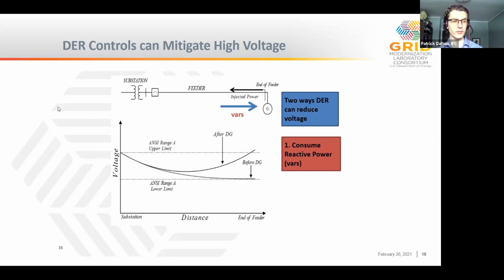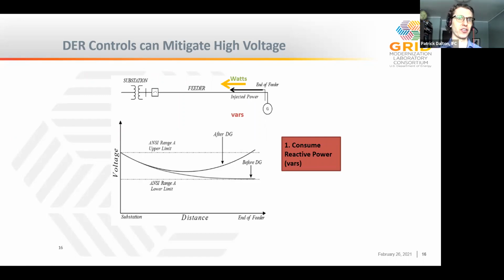The other way, which is a little less desirable, is to reduce the watts — a lower degree of energy production at that time. That's generally reserved as a backup option, because it affects the economics of the DER. And if the system is counting on this energy, it's important to try not to curtail that energy production unless it's absolutely necessary.